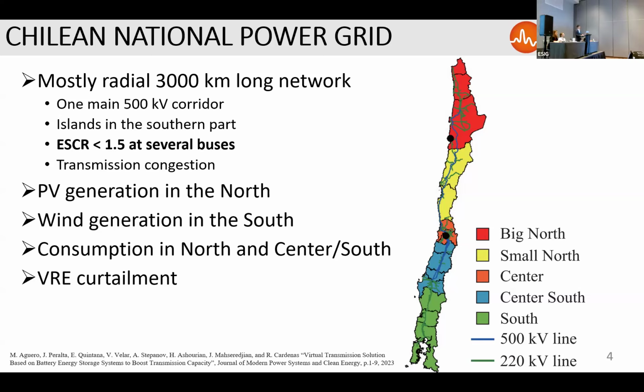Also, another very particular thing about the Chilean grid is that there are some points which are very, very weak. Like there were presentations yesterday mentioning that, well, it's not very good to have SCR below 3. Well, the reality of the Chilean grid is that they actually operate with short circuit ratios below 1.5. So that's something you have to deal with. And because of the way the network is built, because of the way generation and consumption of electrical energy is distributed in the Chilean network, there are congestions that happen often in the transmission system.